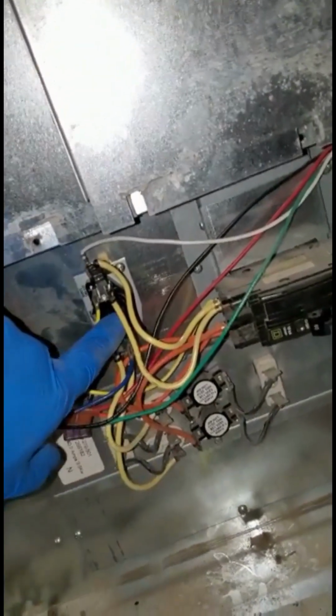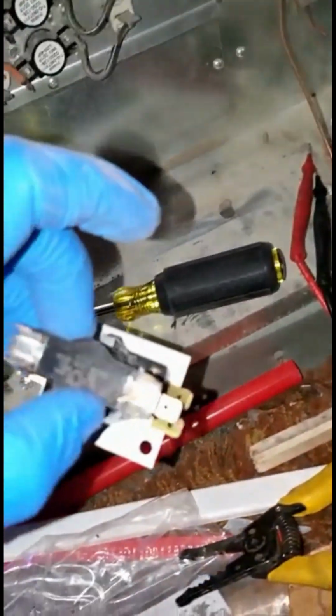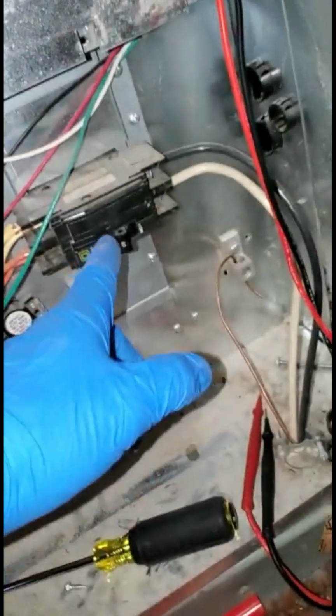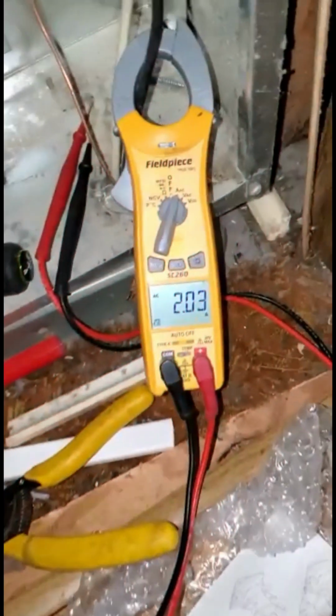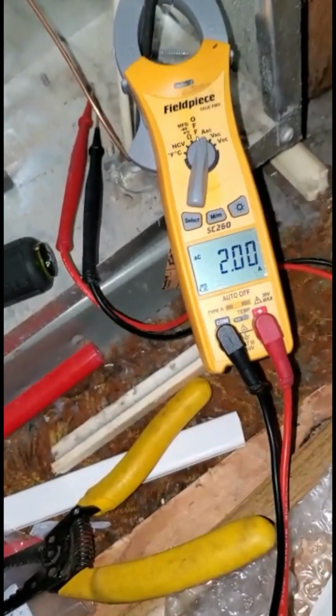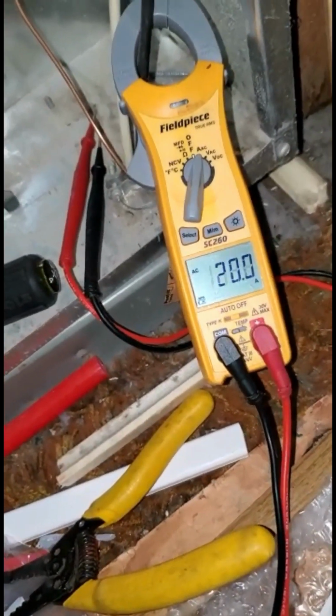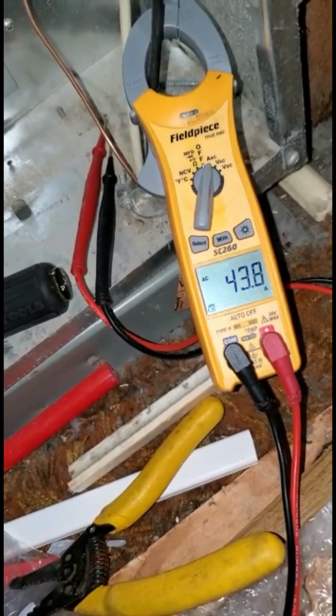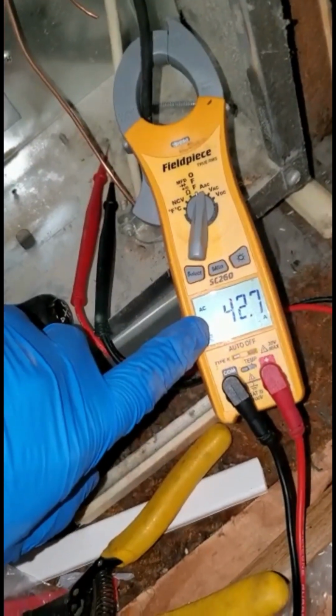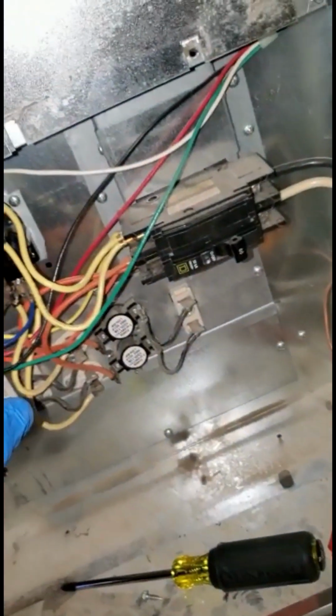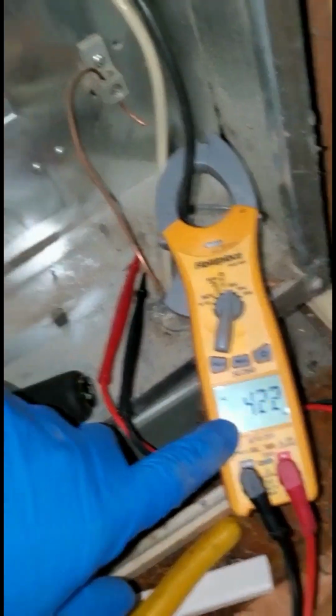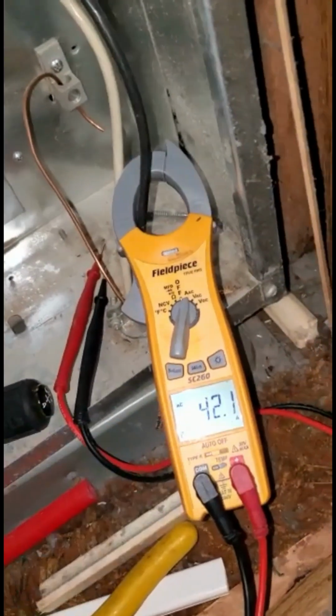Okay, we got the new one in. We've got the old one out, and now we turn power on. So you can see that it's pulling 2.0 amps, but so we've heard the first click and the second click, and now it's pulling 43, almost 44 amps. And so that means that both of those heat kits have energized now. Before we were pulling only 20, now we're pulling 40, full 10 kW.